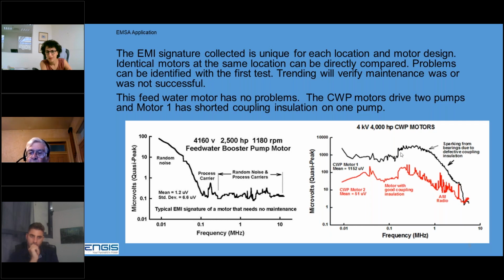But motor number 1, they left the insulation out and they had sparking at the bearings. And that's the difference. So these two can be compared. Obviously, number 1 has a higher reading and a different pattern. I can't see the AM radio stations, so that one needs to be inspected.